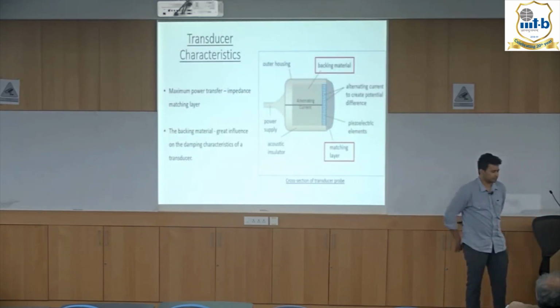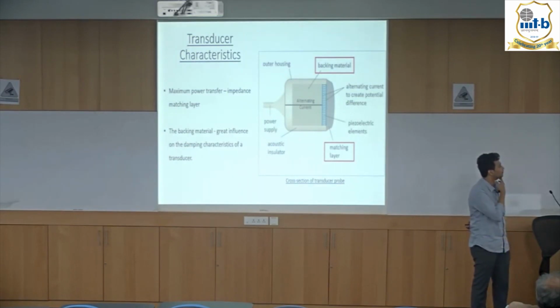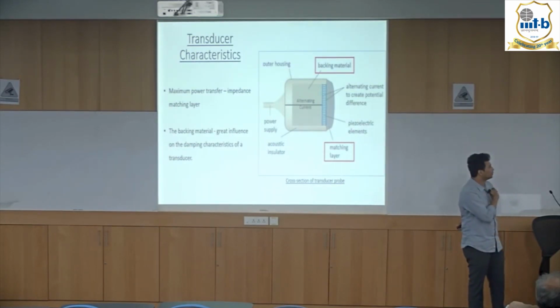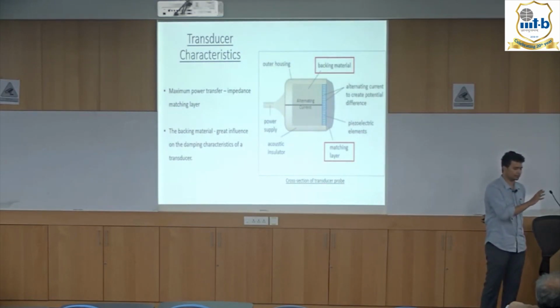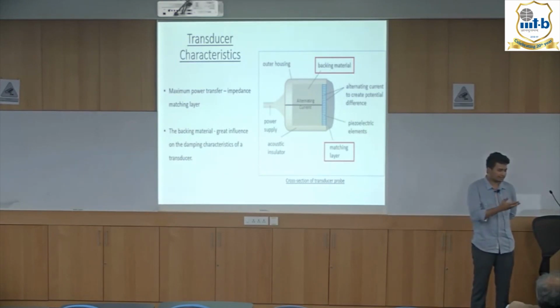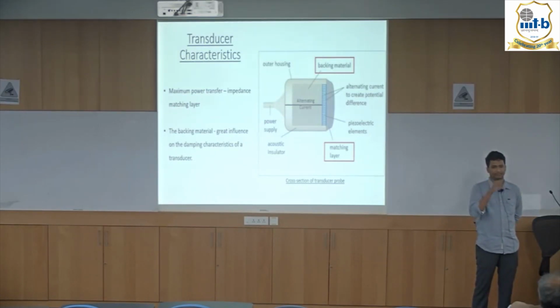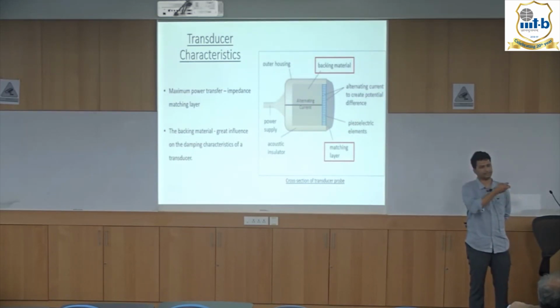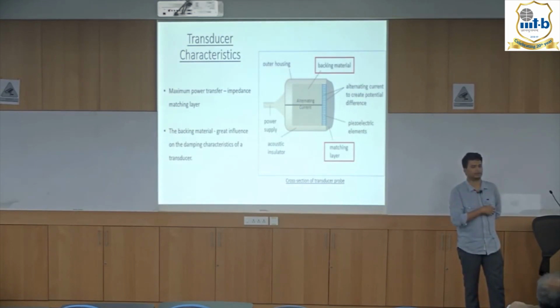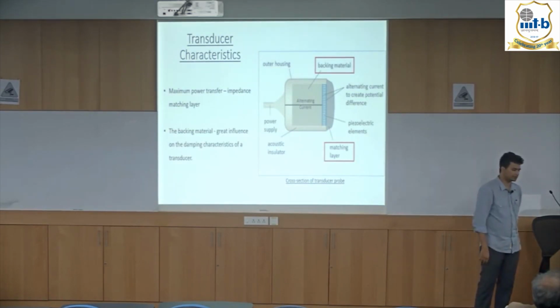So these are the parts which are involved in an ultrasound transducer. There are two important layers in the transducer. One is the backing material and one is the matching layer. The matching layer is present in between the piezoelectric crystals and the face of the transducer. Its presence is predominantly to match the acoustic impedances of the piezoelectric crystal, so that maximum energy is brought out from the piezoelectric crystal.